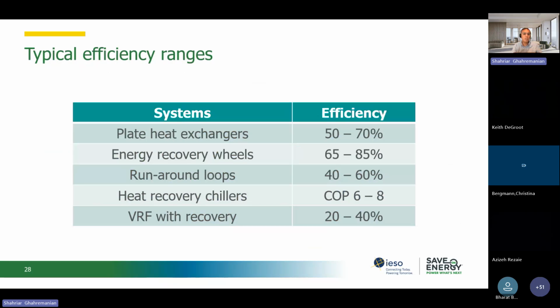Typical efficiency ranges for heat recovery: a plate heat exchanger can be 50 to 70%. Energy recovery wheels 65 to 85%. Run around loops are less efficient, 40 to 60%. Heat recovery chillers have a COP of 6 to 8. And with VRF with heat recovery, you can expect 20 to 40% more efficiency on the VRF systems.